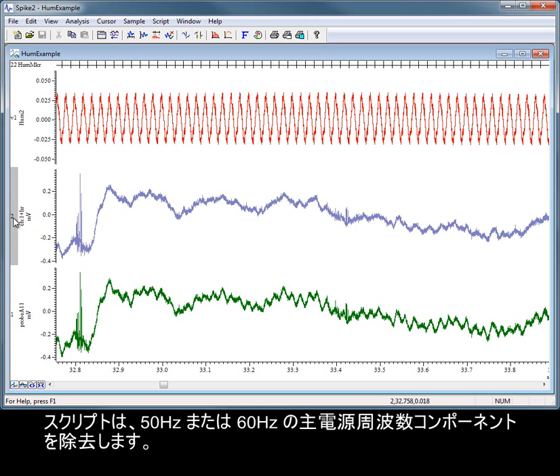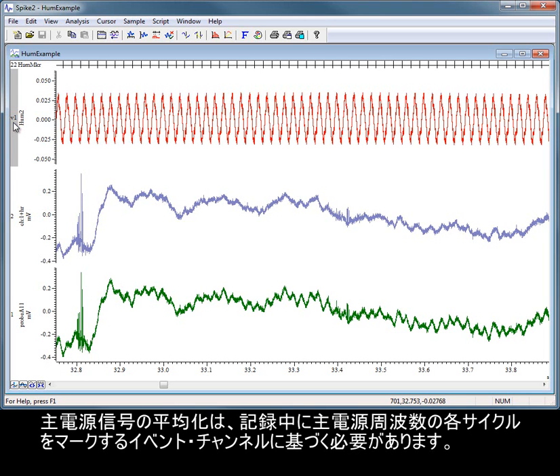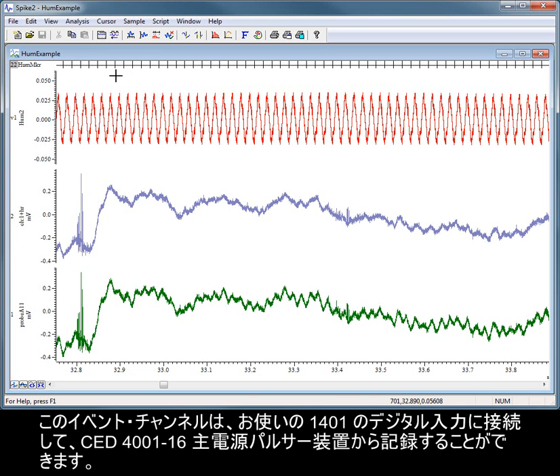The script will remove either 50 Hz or 60 Hz mains frequency components. The average of the mains signal needs to be based on an event channel that marks each cycle of the mains frequency during recording. This event channel can be recorded from a CED mains pulser unit connected to a digital input on your 1401.